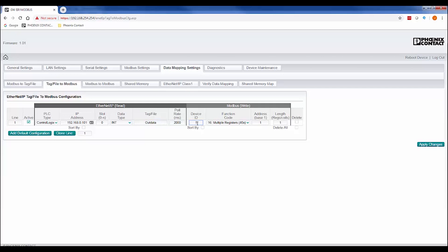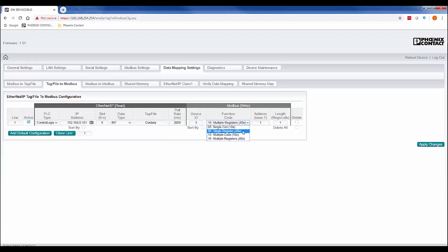On the Modbus write, we'll select ID 3 because in an earlier step, we set up ID 3 to have an association with IP 192.168.0.10. Then, we'll perform a single register write to the address our device uses to access its output with a length of 1. Once complete, we'll apply our changes.